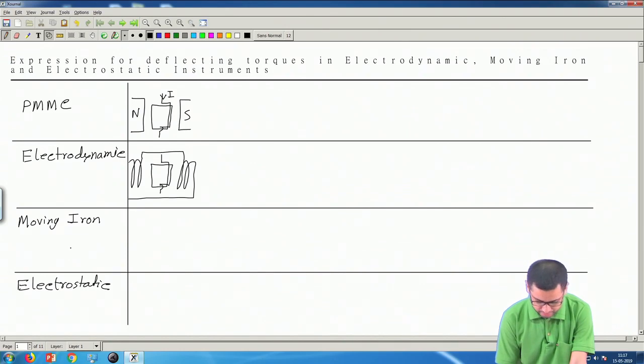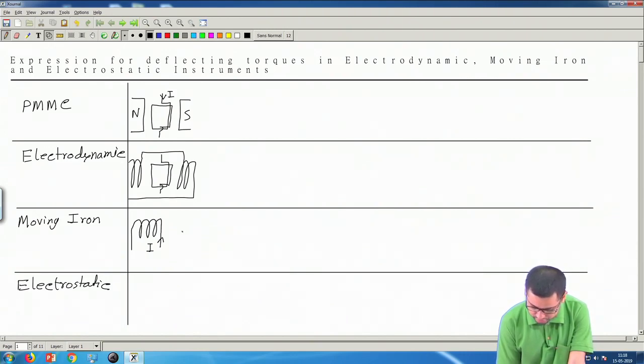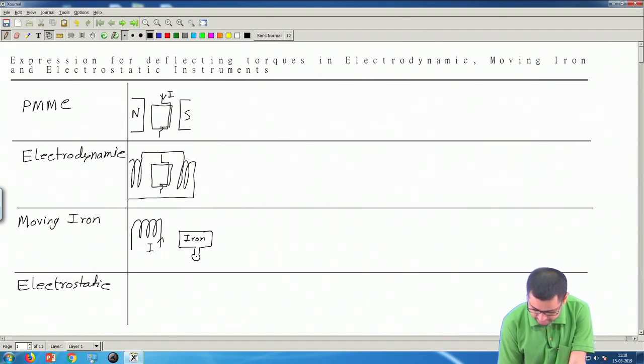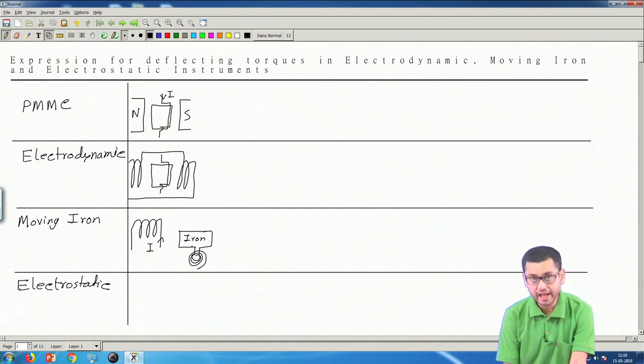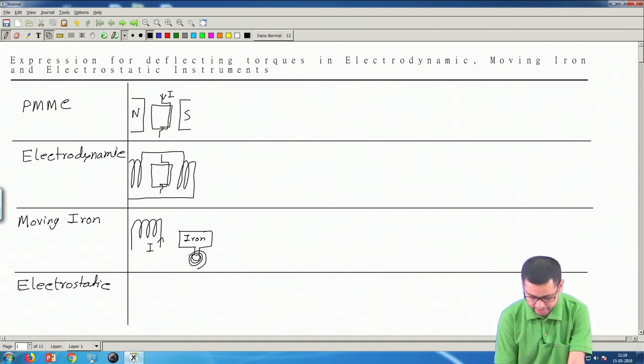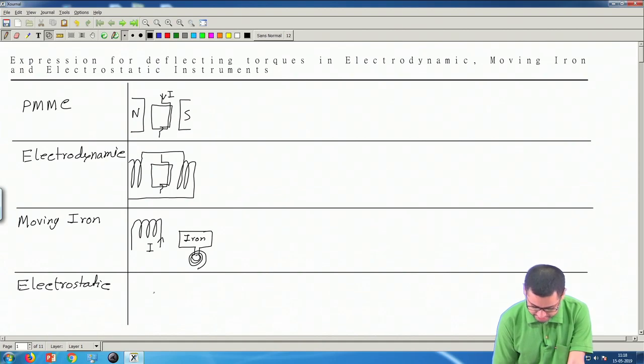The simplest possible scheme is the attraction type moving iron instrument, where we have a coil which carries the unknown current I, and in front of it we have an iron bar that can rotate around a pivot. If any current flows through this coil, it will get magnetized and attract the iron bar. This is the working principle of an attraction type moving iron instrument.